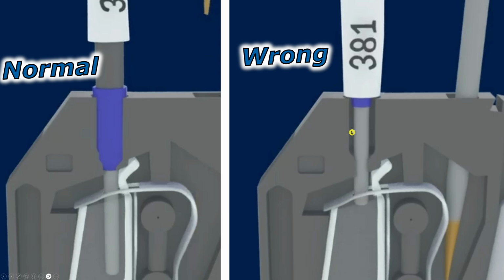But in the case where they put the label too close, you can see what happened. It increased their circumference. So now the purple plastic part of the ferrule cannot slide down into this port opening. So you can't get the connection. And so this is the result. This is what happens. You don't get the ferrule going all the way down and all the way through. So you get enough vibration and some heavy seas over the years, and it's enough to start wiggling this thing loose. The next thing you know, it pops up a little bit, and you have a gap, and then you can end up with arcing.